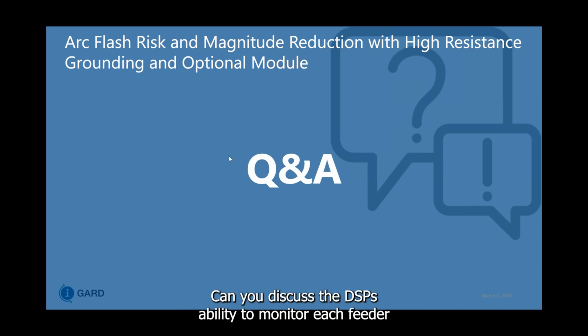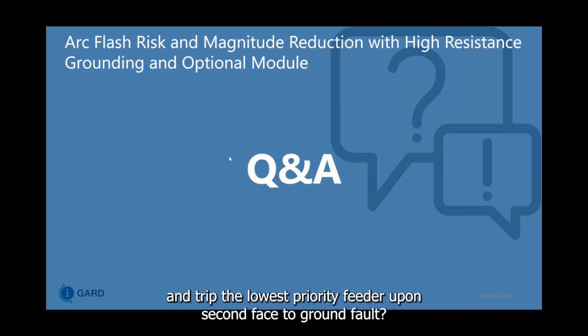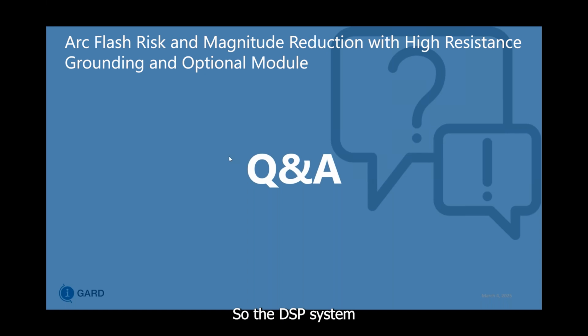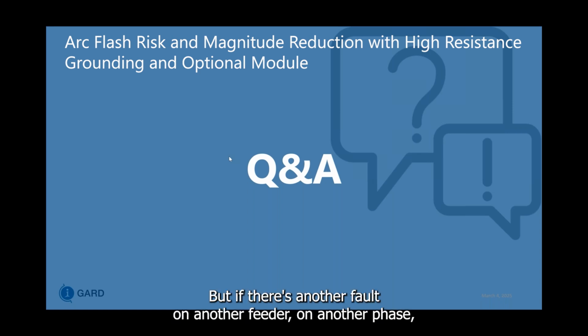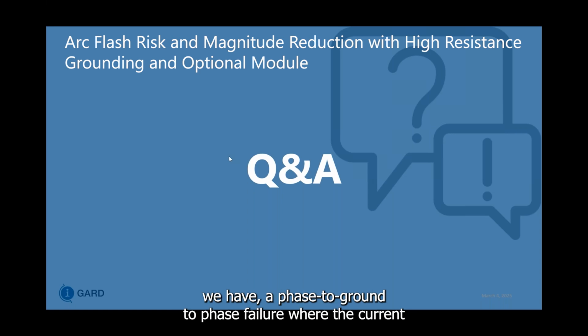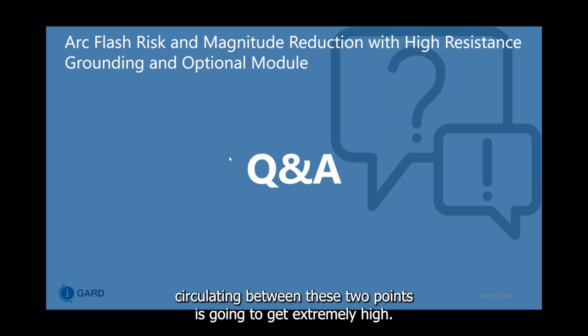Can you discuss the DSP's ability to monitor each feeder and trip the lowest priority feeder upon second phase to ground fault? We can, for sure. So the DSP system, upon first fault, you don't have to trip because the fault is being limited to 5 or 10 amps as a standard. But if there's another fault on another feeder on another phase, we have a phase to ground to phase failure where the current circulating between these 2 points is going to get extremely high.